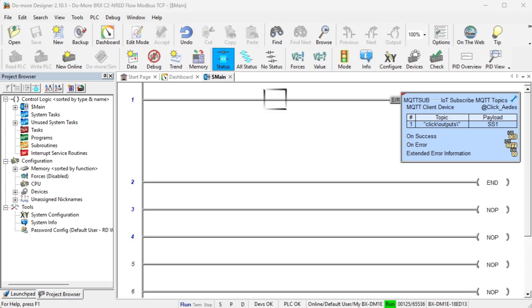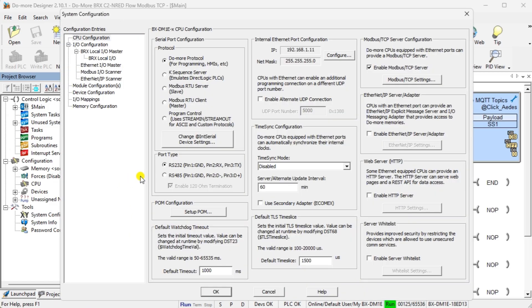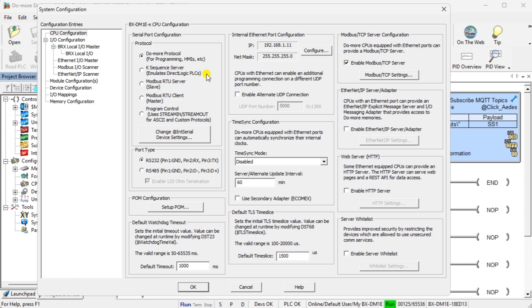Call up the system configuration in DoMore Designer programming software. Select the system configuration under Tools in the project browser menu — this can also be selected from the main menu under PLC System Configuration. The system configuration window will be displayed. Under the CPU configuration selection, which is the default, you will see the internal Ethernet port configuration, which shows the current IP address that has been assigned.